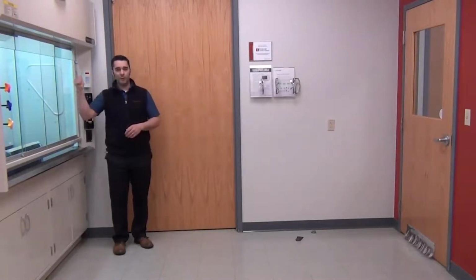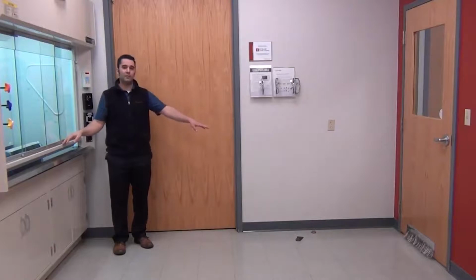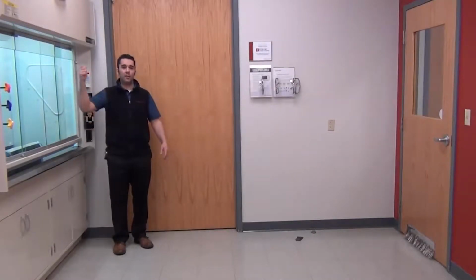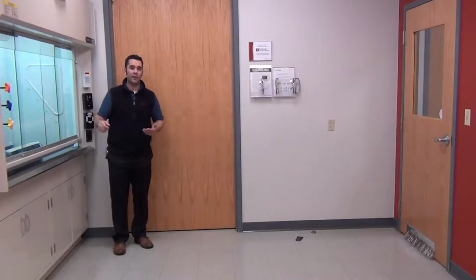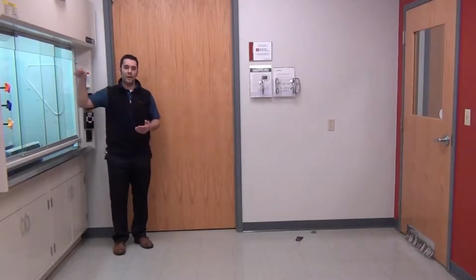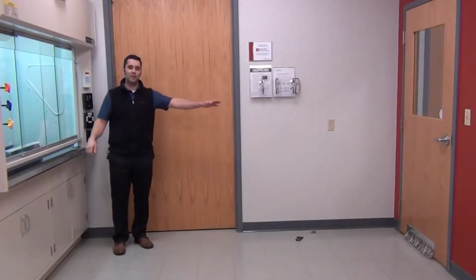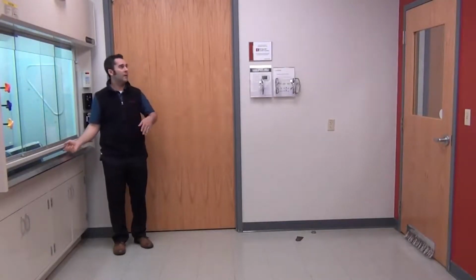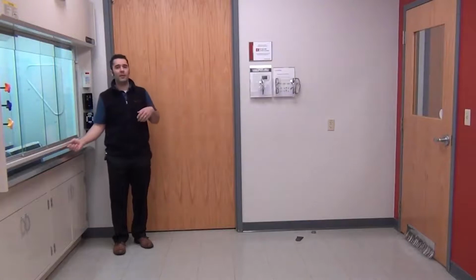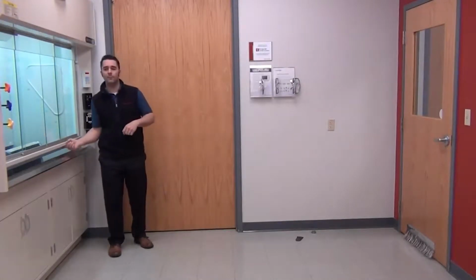So as I open my fume hood, I want you to pay attention again to the hula skirt. You're going to see that when I open my fume hood, it's going to be very negative in here for quite a long time. And as I close my sash, you're going to see that that hula skirt is actually going to go neutral and slightly negative and then slowly come back. So again, my pressure on my magnehelic gauge right now is settled out at 0.02.